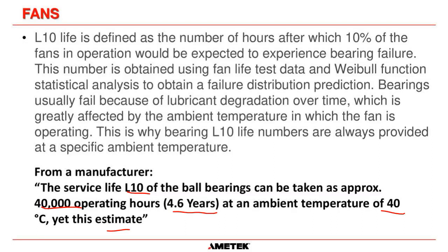We went to the data sheet, we checked the ambient temperatures that we expect the fans to operate at, and it was decided that a 5-year span is suitable for our capacitors. So once again, I mean for our fans. Once again, we're not making these numbers up. These come from the manufacturers of the capacitors and the fans that we use. So that is why we have the schedule in place to replace them at those times.